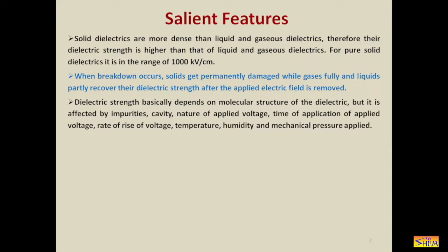Dielectric strength basically depends on the molecular structure of the dielectric, but it is affected by impurities, cavity, nature of applied voltage, time of application of applied voltage, rate of rise of voltage, temperature, humidity, and mechanical pressure applied. But basically, it is severely affected by the impurities and cavity inside the dielectric.